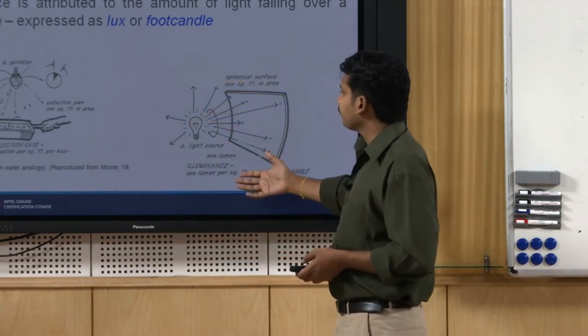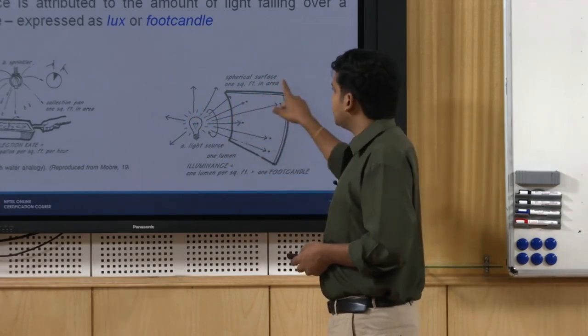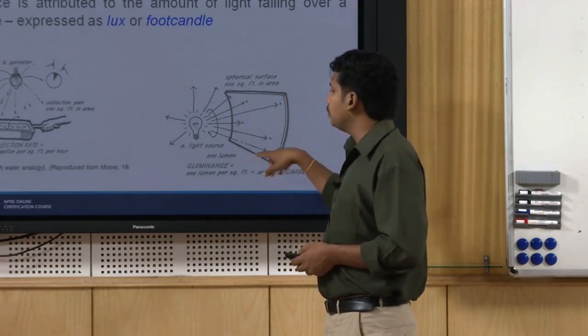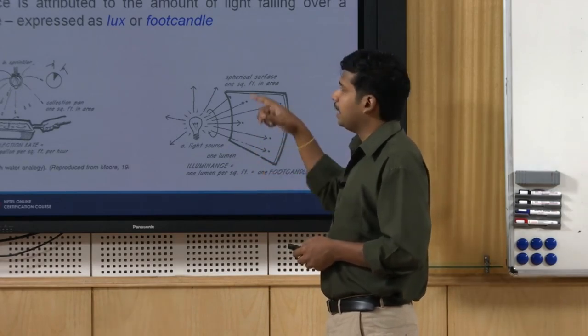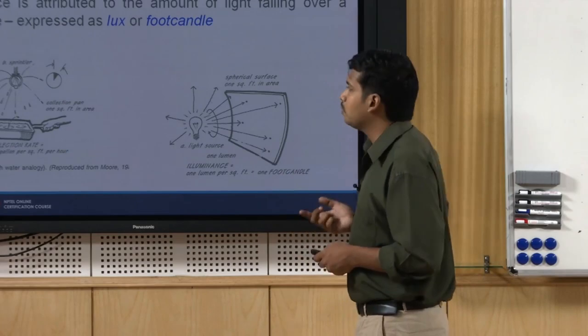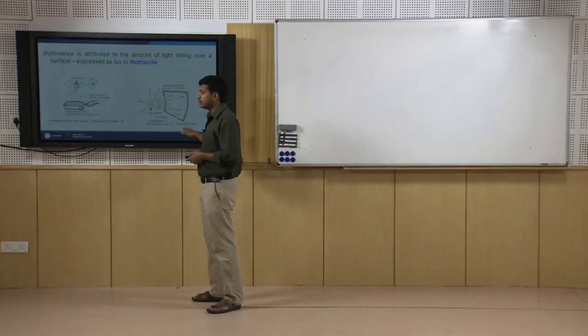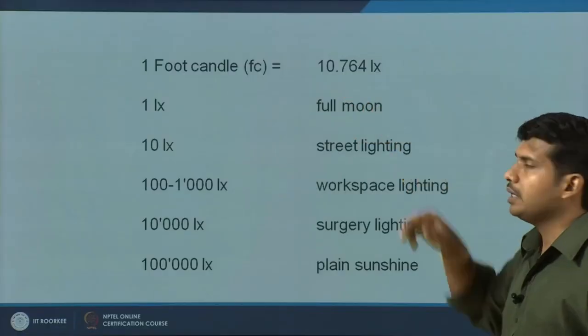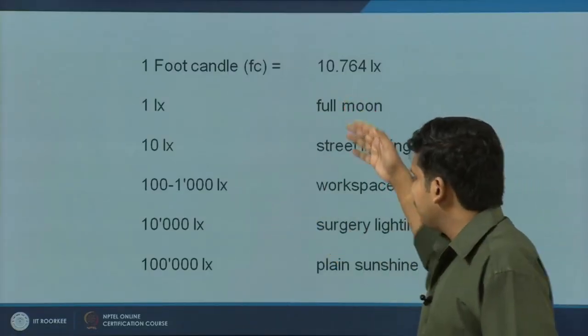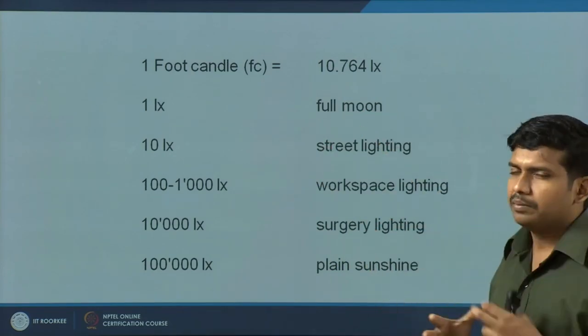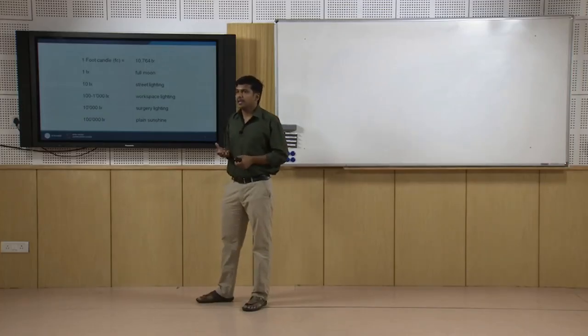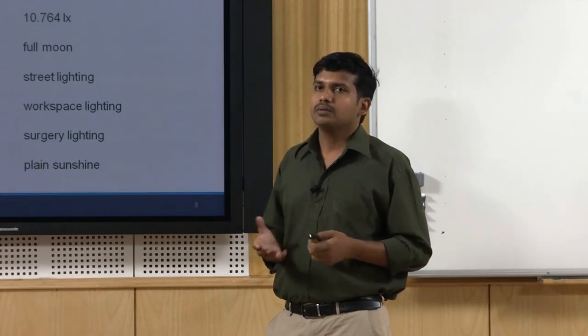In the same way, if you have a plane on which light energy is falling, how much luminous flux will fall on a particular area — lumens per square meter — is indicated as lux level. A full moon gives close to 1 lux — a very low light level. Indian standards recommend around 300 lux for typical reading and writing activities, such as classroom lighting; students' tables should have around 250 to 300 lux.